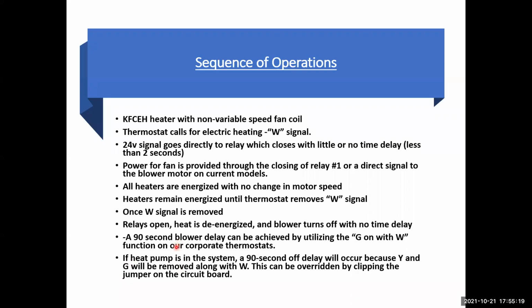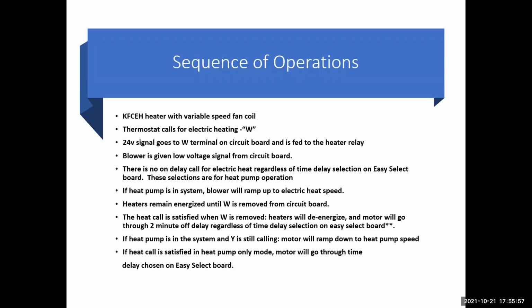A 90-second blower delay can be achieved by utilizing the G on with W function on our corporate stats. So if you have that thermostat, you will be able to get that. Now, if the heat pump is in the system, a 90-second off delay will occur because Y and G will be removed along with W, and this can be overridden by clipping the jumper on the circuit board. KFCEH heaters and variable speed application.